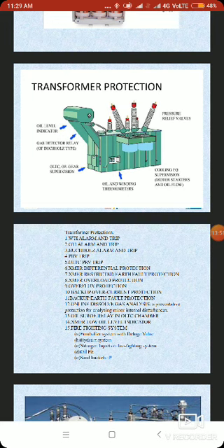Then transformer differential protection, transformer restricted earth fault protection, transformer overload protection, overflux protection, backup overcurrent protection, backup earth fault protection, online dissolved gas. This is an online monitoring technique. Dissolved gas analysis is one of the online monitoring techniques. We have three or four techniques for that, but we'll just discuss dissolved gas analysis, because this is a very important aspect. Then we have the oil surge relay in the OLTC chamber, and transformer low oil level indicator.